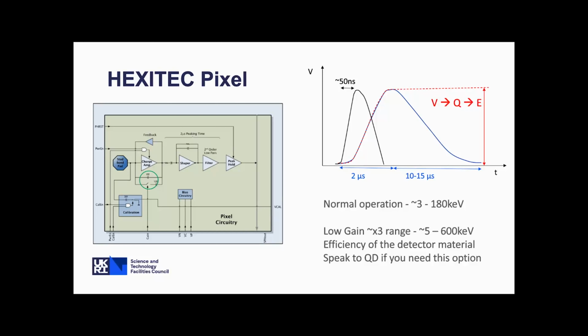It's also worth noting, and we'll come back to discuss this later, that the recovery of the preamplifier is also seen in the recovery of the shaper. And that's another slow process, which becomes a factor in how we operate the detector later on. The other thing worth noting is that the energy range that we achieve is about 3 to 180 keV per pixel. And for those who have eagle eyes, there is a switch in here, so you can change the gain of the amplifier. That would go to a lower gain, so we go out to around 600 keV per pixel. That isn't something that we typically use because we're limited by the detector material efficiency. But if you're interested in that high energy range, it's worth speaking to Quantum Detectors about, I know they might be able to accommodate that as well.